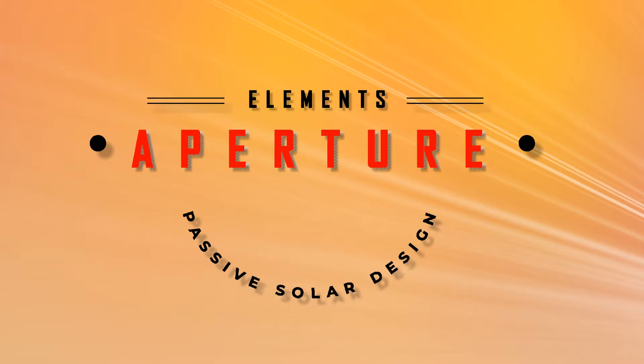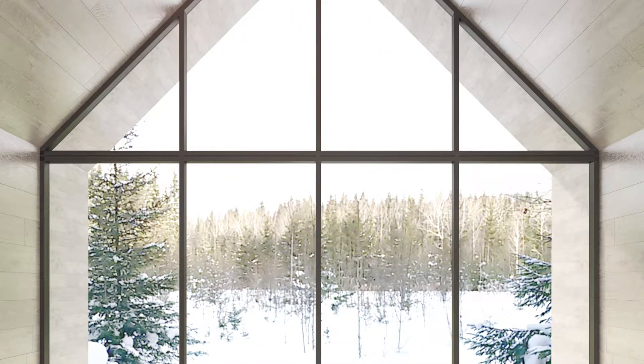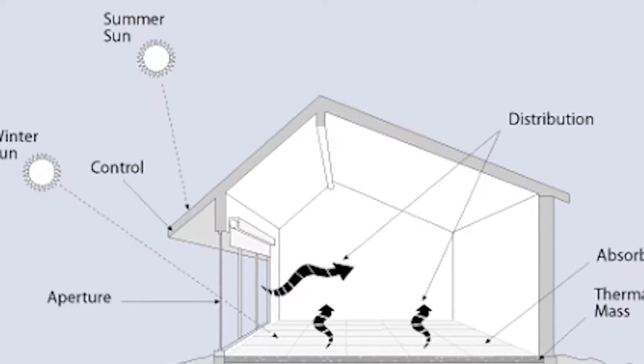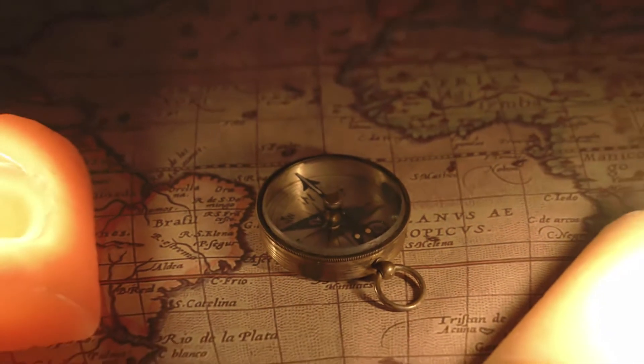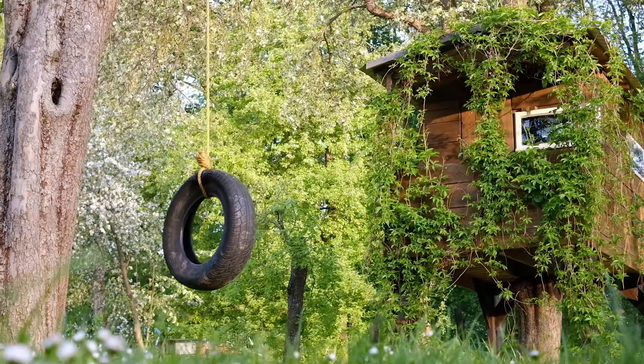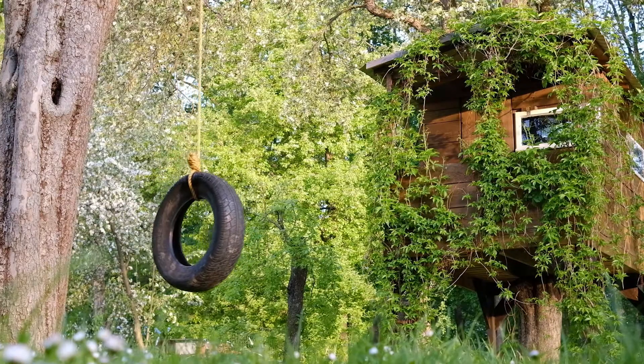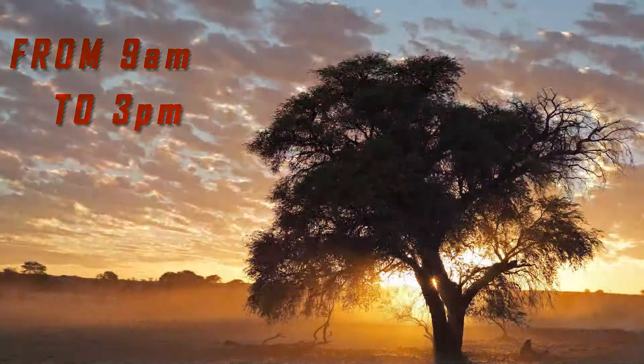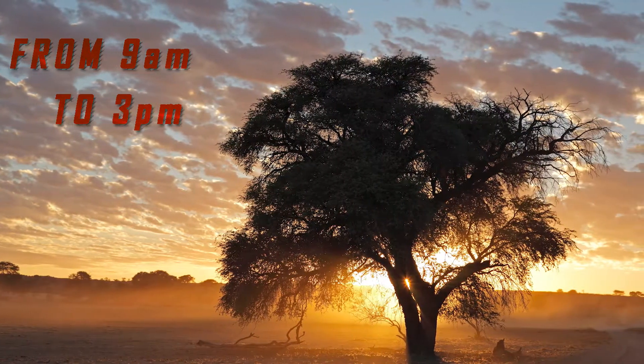Number one: Aperture, otherwise described as a collector. It is a large glass area through which sunlight enters the building. Typically the aperture should face within 50 degrees of true south and should not be shaded by other buildings or trees from 9 am to 3 pm each day during the heating season.